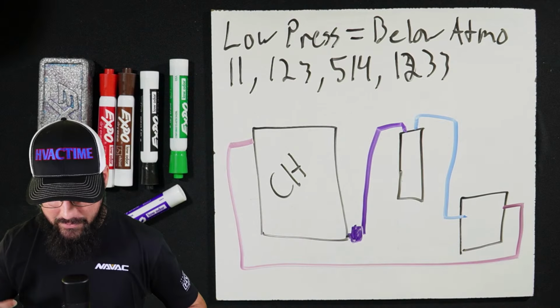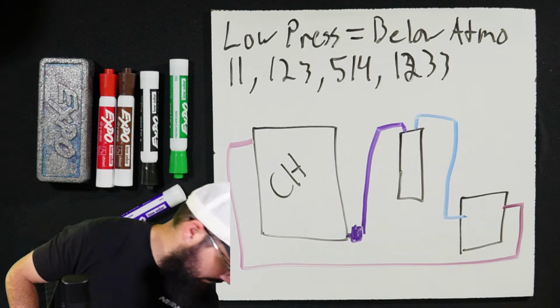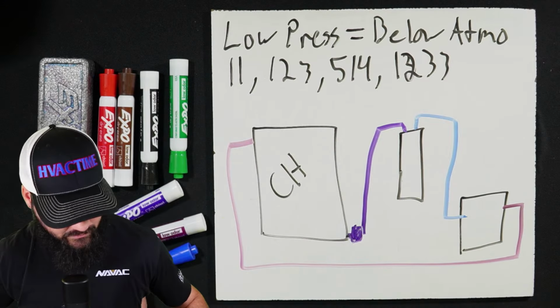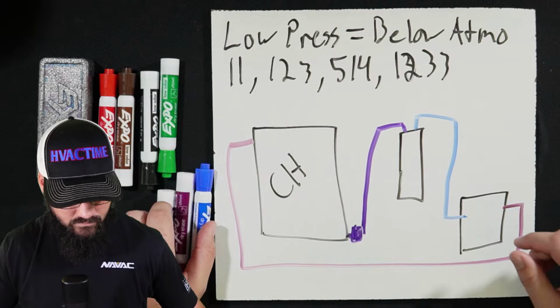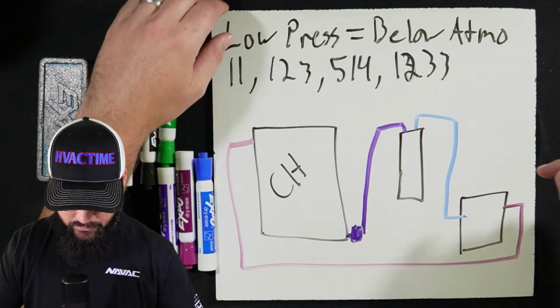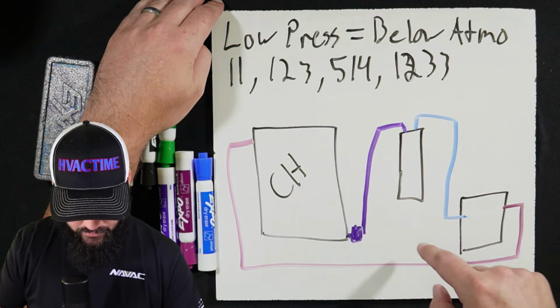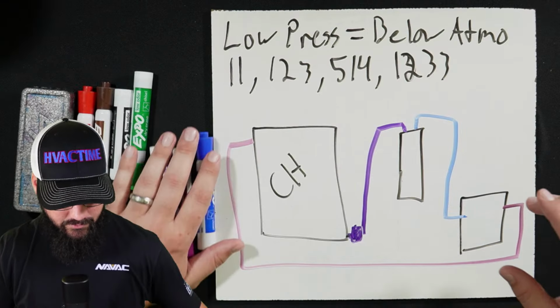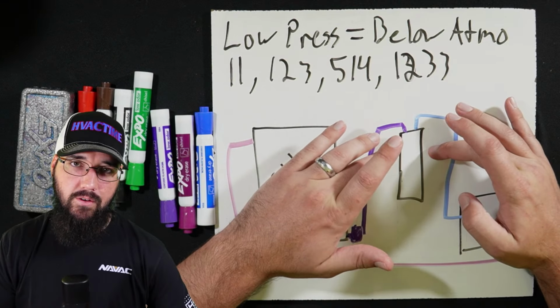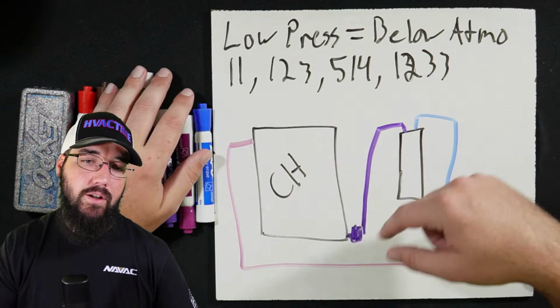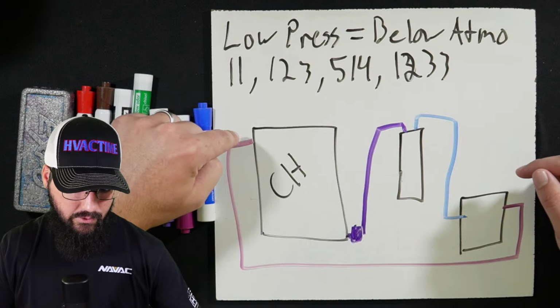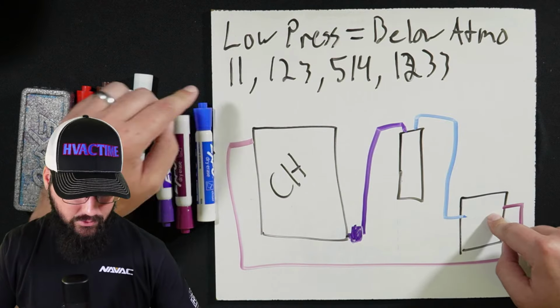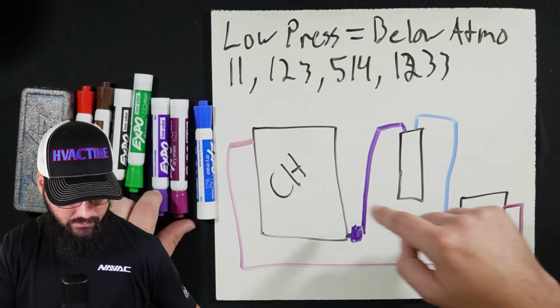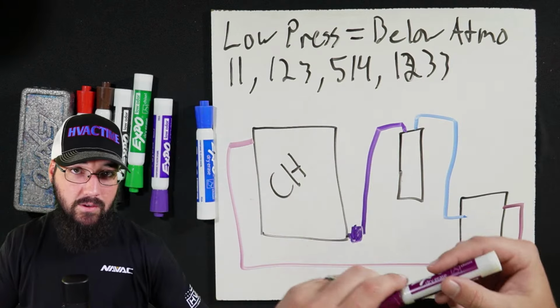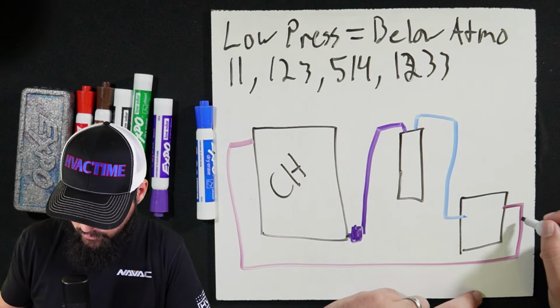We're going to flip this the other way around. I don't need to change any of the colors here. We'll just point it the other way. So in a charging scenario, all of our refrigerant is in this cylinder. We want to get the refrigerant out of this cylinder into the chiller. We're going to connect the exact same way. We're going to have our inlet to the recovery machine come off of a vapor port. Like I said, that suction elbow port, something like that, is always really handy.